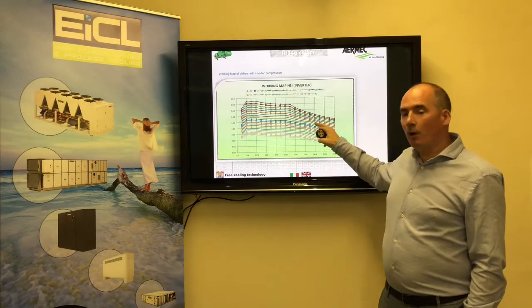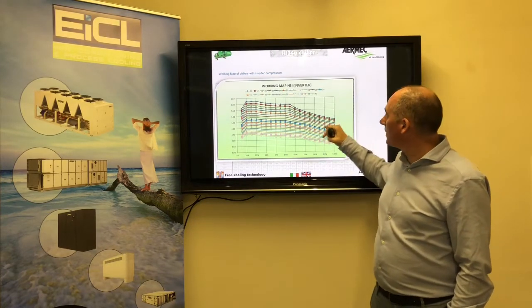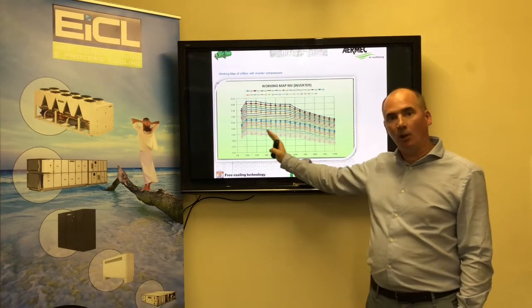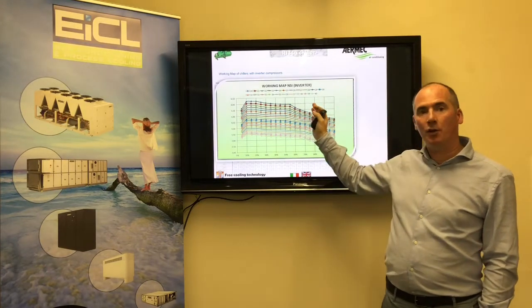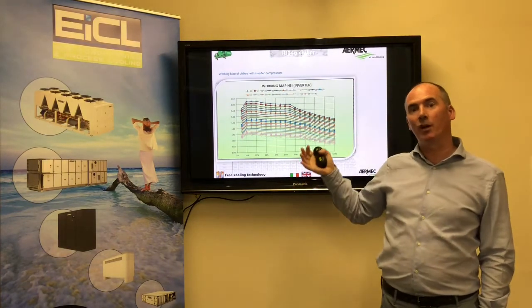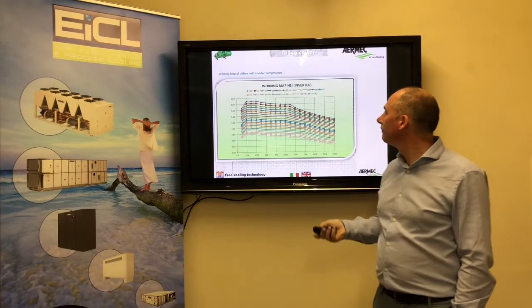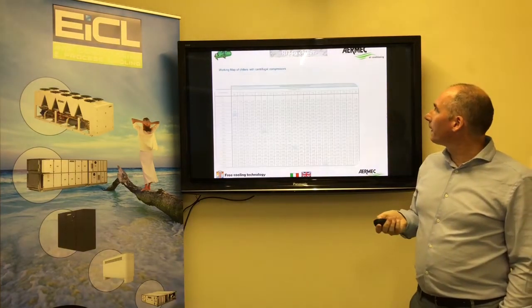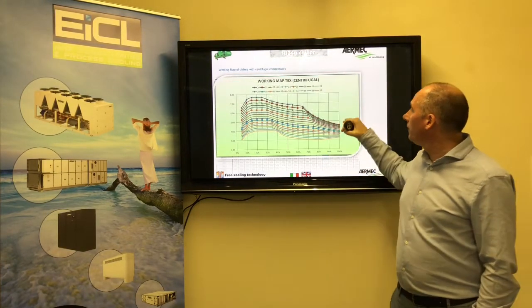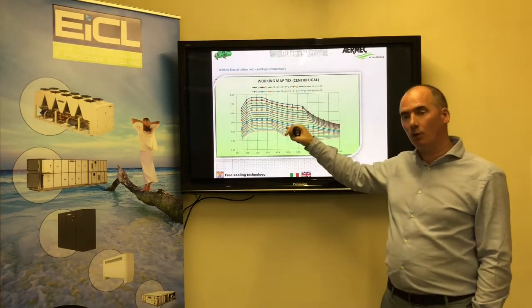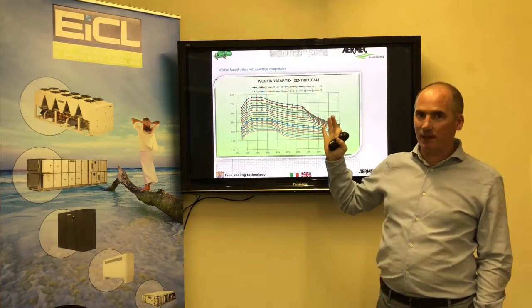And you'll see the inverter screw has an improving efficiency almost consistently in part and low load. So obviously that's a really good option, especially for an application where you expect to be running in low load. The Turbocor, finally, is far superior in part and low load. Consequently, it's a lot more expensive as well.